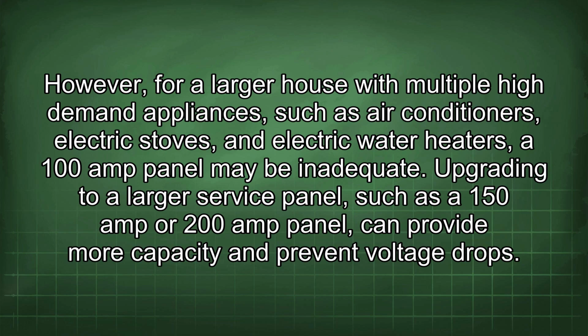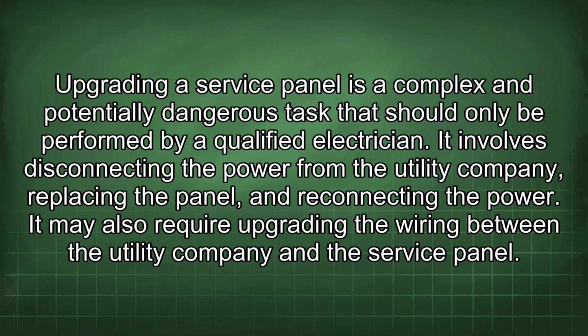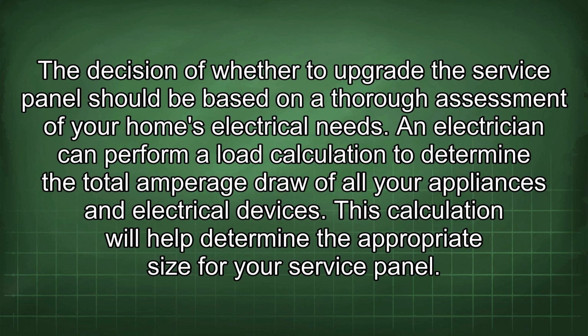prevent voltage drops. Upgrading a service panel is a complex and potentially dangerous task that should only be performed by a qualified electrician. It involves disconnecting the power from the utility company, replacing the panel, and reconnecting the power. It may also require upgrading the wiring between the utility company and the service panel. The decision of whether to upgrade the service panel should be based on a thorough assessment of your home's electrical needs. An electrician can perform a load calculation to determine the total amperage draw of all your appliances and electrical devices. This calculation will help determine the appropriate size for your service panel.